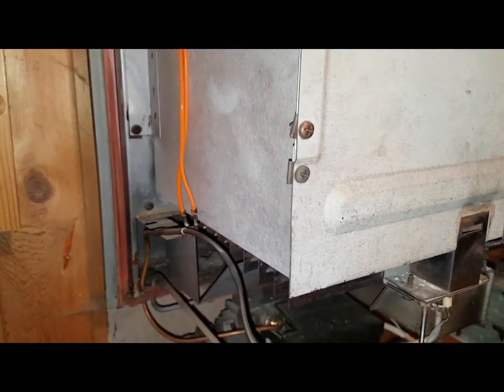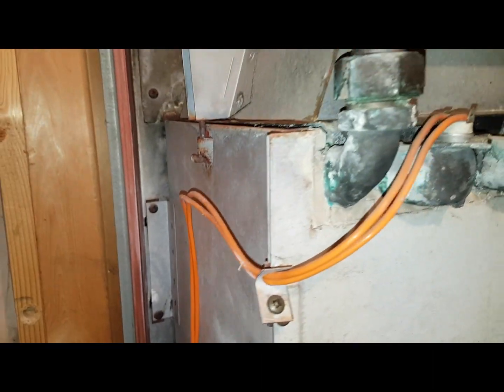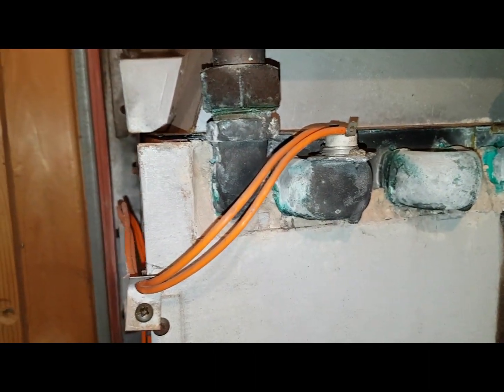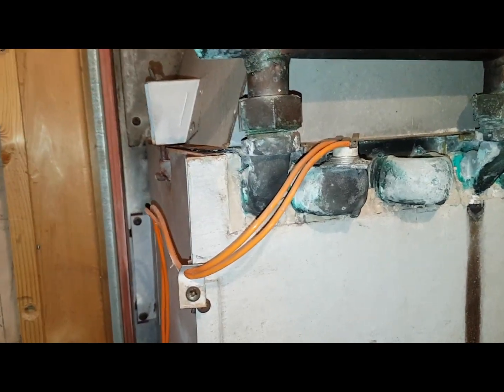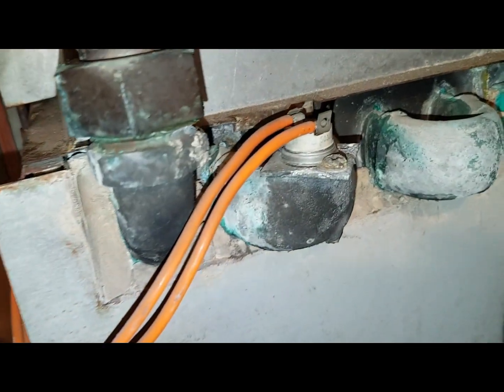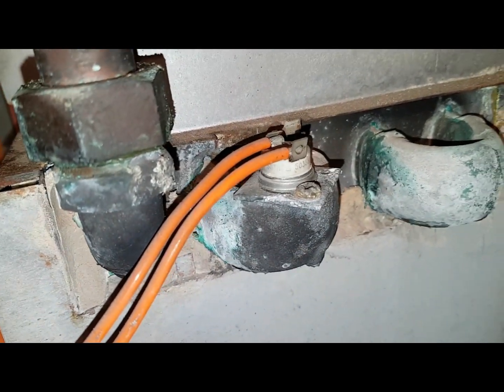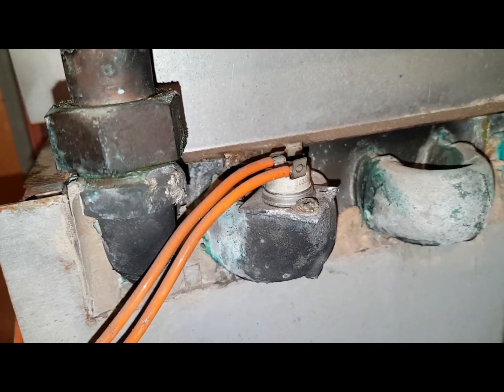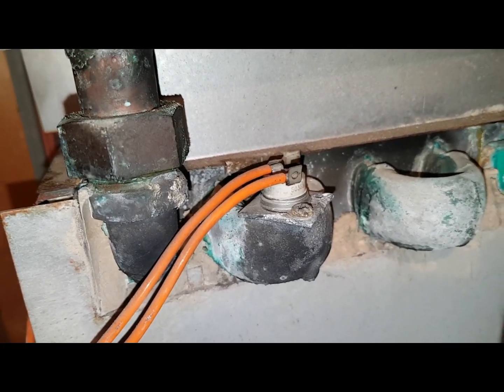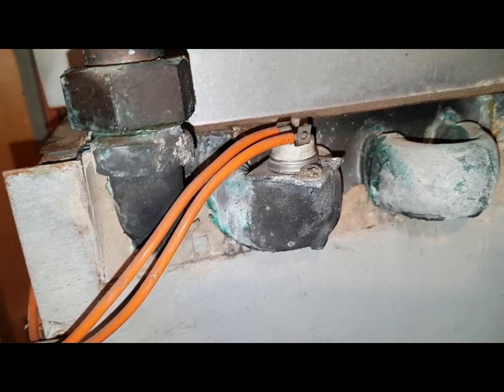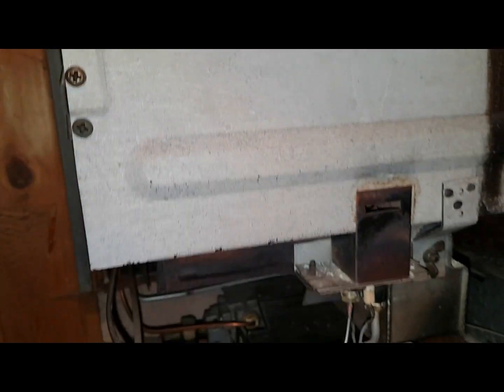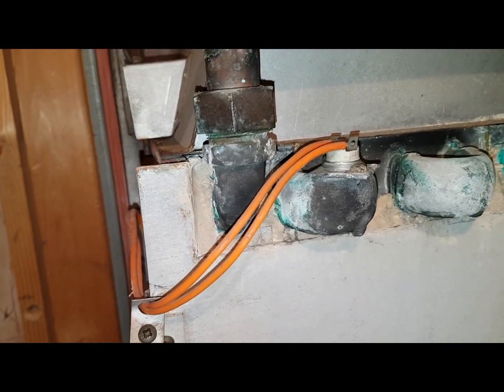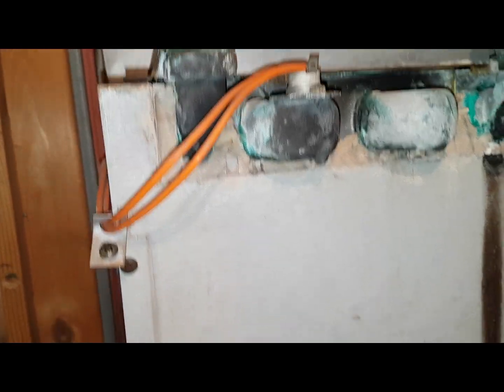As I said, you don't see that often on boilers, but it's something to know and understand on these types of boilers. Now, I have seen in the past where people have bypassed this, linked that together, making the boiler dangerous because it's got no protection. So if it was to overheat, there's nothing to shut the pilot light off. If you ever see that situation, it is very dangerous, and that person should be reported. So something to watch out for.